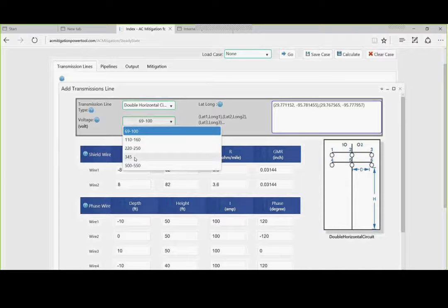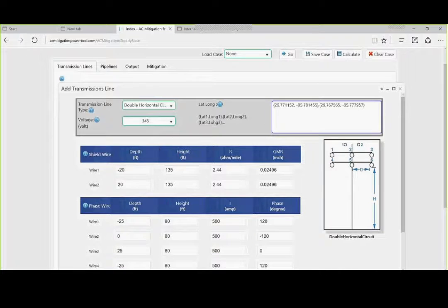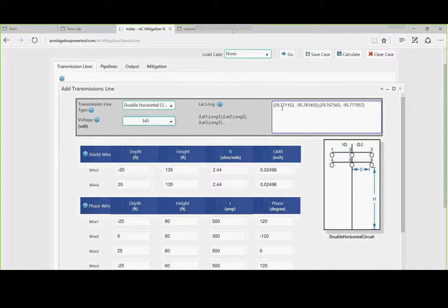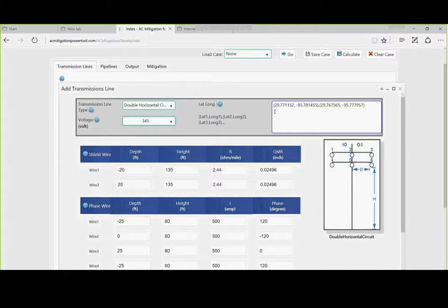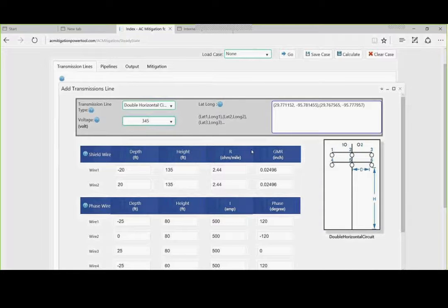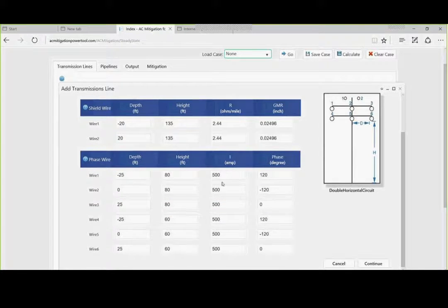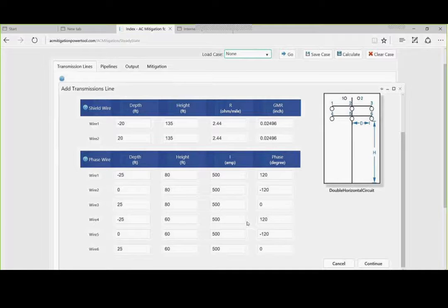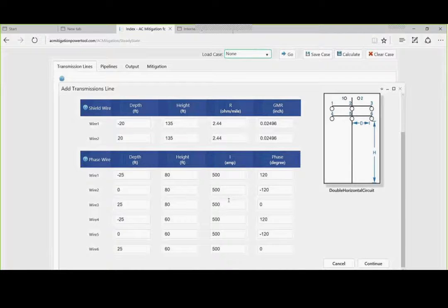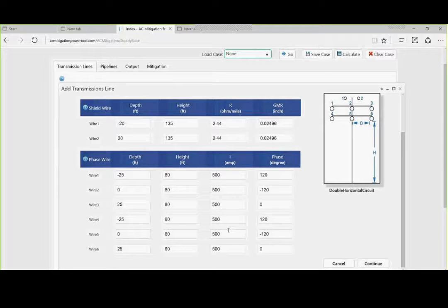Let's take a 345 kV system. And if you notice up here in the right-hand corner of add transmission lines, we have some lat longs in here in decimal degrees. And if you notice, they are separated by commas and parentheses. We have a beginning lat long and an ending lat long for the transmission line. And if you notice that the currents, and this is the key, this is defaulted. These can be changed. Almost anything on this data input could be changed. And the reason for it is because power transmission lines operate at different currents during seasonal changes. For the purpose of this, we are going to accept the default of 500. But it is not uncommon to have 750 amps during the summer for this type of a transmission line.